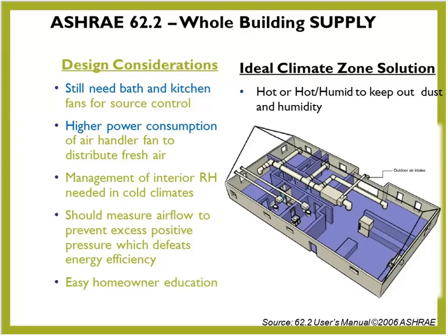So pushing it through a building shell where it will come in contact with cold surfaces, especially in Michigan, Wisconsin, where we can get 0 and below during the wintertime, we want to be cautious about how much pressure we're putting on the building to push that warm, moist air out through the building shell. So maybe not as ideal an approach for northern climates as it would be for the south.